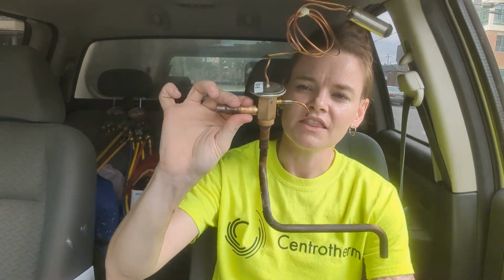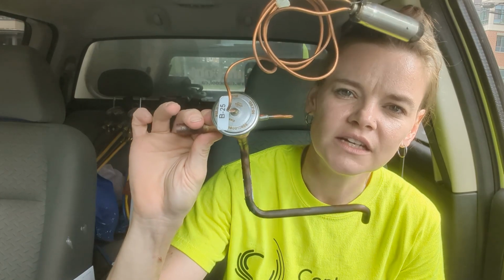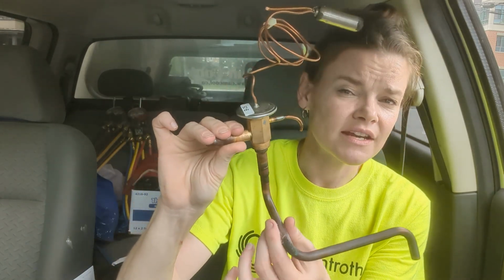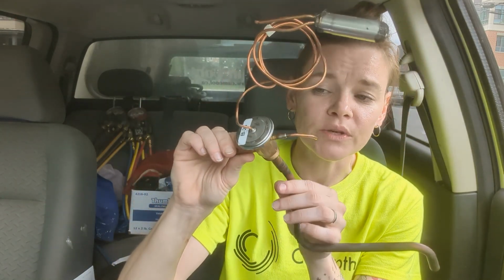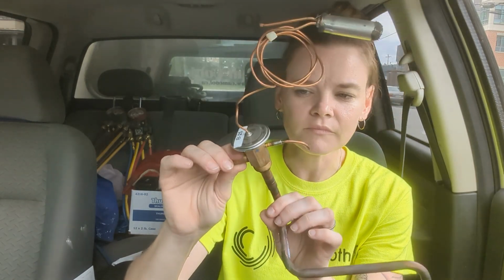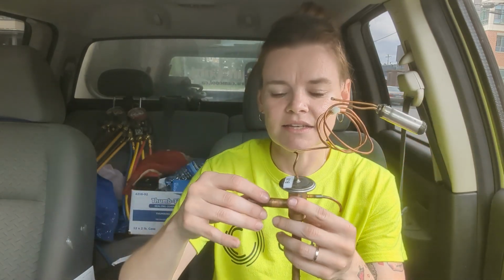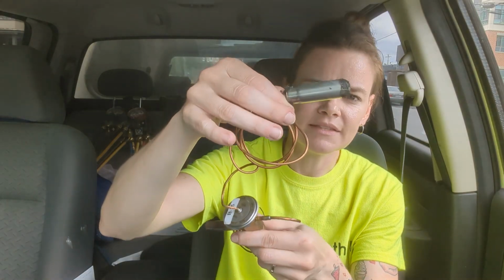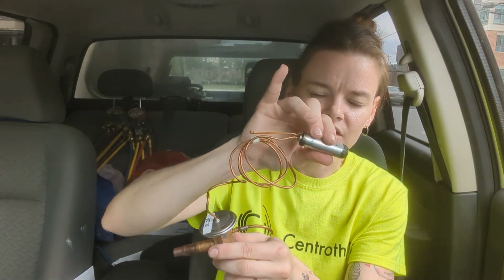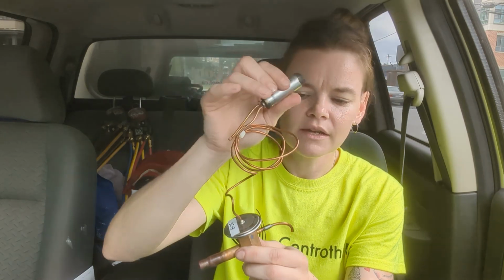Actually, I've got show and tell for you this week. We had to replace the TXV, and this is the TXV - it's this thermostatic expansion valve. It's basically the metering device component in a refrigeration system. In a super basic way, it lets through as much refrigerant as needed into the evaporator. There's this little sensing bulb that gets attached to the suction line on the other side of the evaporator.